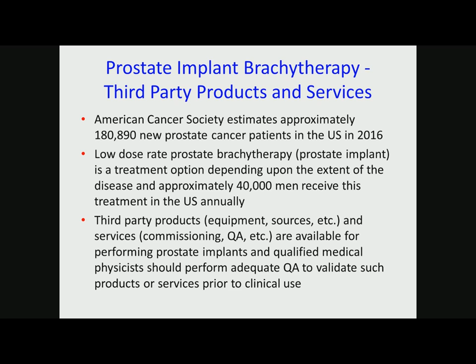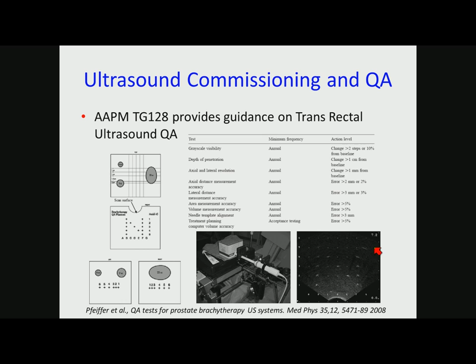Again, this is not correct. You as a physicist need to learn ultrasound, how to use it. You need to commission the equipment. You need to do annual QA. TG128 is a very good document, completely dedicated to ultrasound QA. And so you should go in and you can get a CIRS Phantom. It's an ultrasound phantom, which has different wires running through it and different prostate sizes that you can use in QA. You can also create a grid using it, and they give you some action levels.